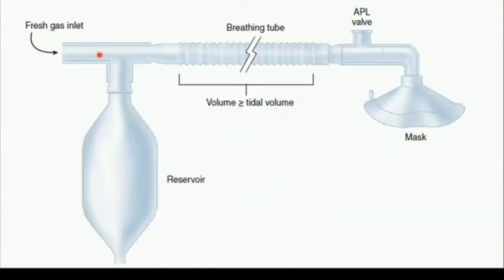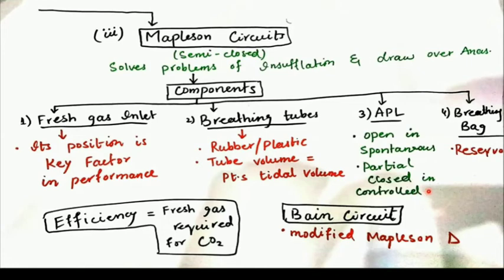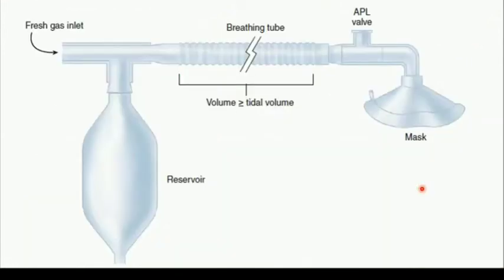During spontaneous ventilation, fresh gas is continuously coming in and when the patient exhales, the valve should be open to let the gases out. During controlled ventilation, the APL valve should be closed during inhalation to build the required pressure, and open during exhalation to let the gases out.